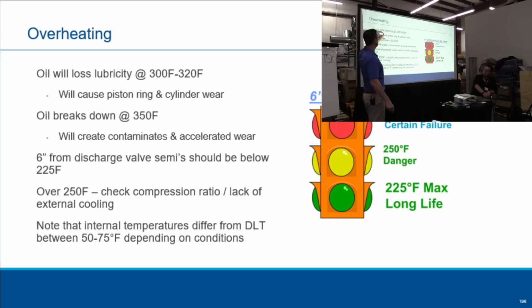Oil will lose lubricity at 300 to 320 Fahrenheit. Right? Dave said earlier, 6 inches from the compressor, 225 on our semi-hermetics. Right? Because inside the head, it's 50 to 75 degrees hotter. So now I'm in that danger zone. Is everybody following me? So now oil breaks down. POE oil at 350 will create contaminants and accelerate wear. So 6 inches from the discharge for semis should be below 225.